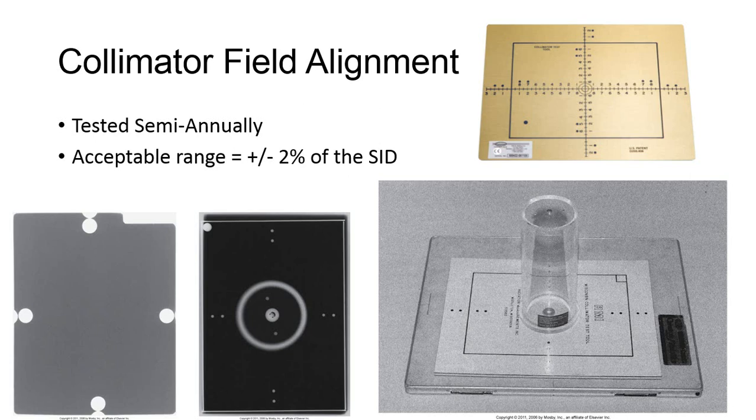If you don't have this test tool available, you can perform what's called a 9-penny collimator test, seen on the left. Using a clean image receptor, you can collimate to a square smaller than the image receptor size.